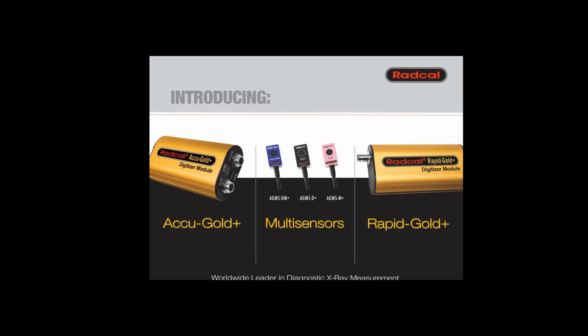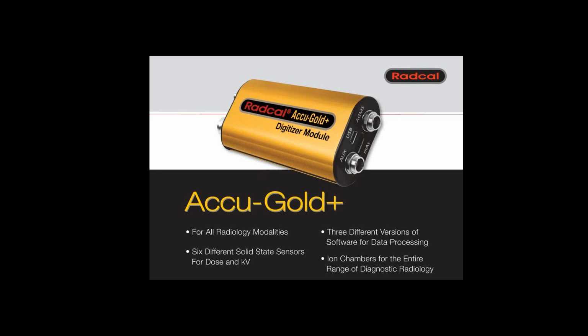The heart of the Accu-Gold+ is the Accu-Gold+ Digitizer Module, and to it the multi-sensors, ion chambers, light meters, and even adapt checking devices can be attached. Each sensor has its own unique connector to avoid connection confusions. It connects directly to your laptop, PC, or tablet for quick data processing, presentation, and report generation. There's no need to transmit the data from your device to another computer for report generation. The Accu-Gold+ will perform measurements for all modalities, that is diagnostic X-ray, fluoro, mammography, dental, and CT.